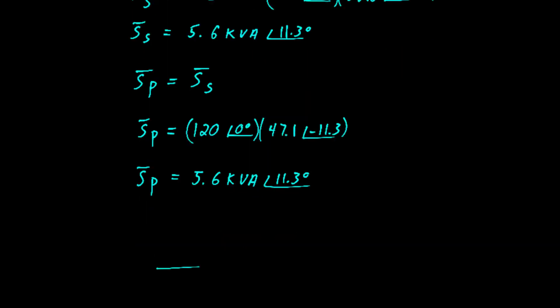We can sketch the power triangle for this inductive load. Here's our 5.6 kVA at 11 degrees. And I find it useful to put these into terms of real power, which is 5.5 kW, and reactive power, which is 1.1 kVAR.